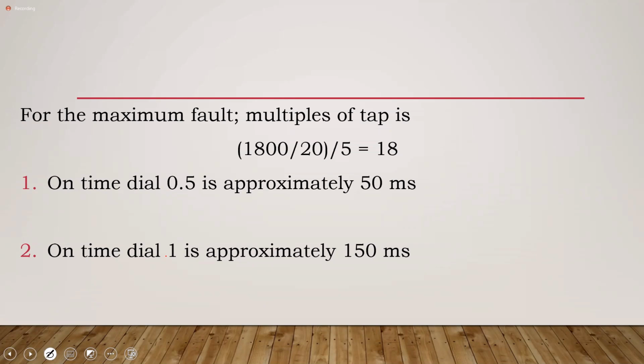But to just complete the last couple of slides, I'm going to do that because it deals with the other protection. I have dealt with overcurrent. We started out telling you about magnitude measurement relays, then product measurement, and ratio measurement. So I've just looked at the magnitude, which is the overcurrent relay. I just want to talk briefly about some other relays. And if you have to leave, you can pick up the information from the recording, but it's not a lot.